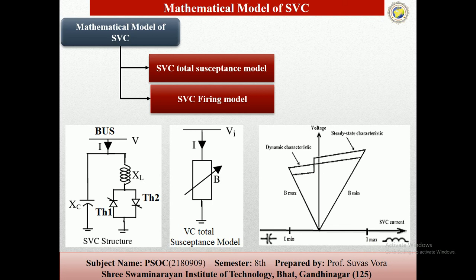The slope is typically 2.5 to 6.5% at the capacitive limits, and the SVC becomes a shunt capacitor. At the inductive limits you can see that it becomes a shunt reactor. So these are the dynamic characteristic and these are the static characteristics, because here you can see the minimum value where we can put the capacitors and the maximum for the inductors.